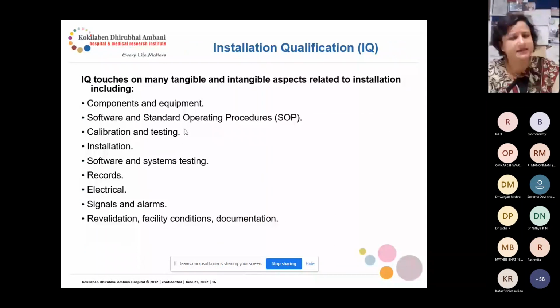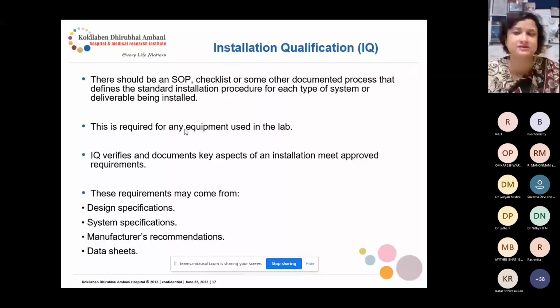So at various stages during IQ, you need to review, check, report, and authorize the protocol. You need to check the specification and the acceptance criteria. IQ touches many tangible and intangible aspects related to installation, including components and equipment, software and the standard operating procedure for your software, calibration and testing, installation, software and system testing, records, electrical testing, signals and alarms, revalidation, facility conditions, and documentation. So there should be an SOP, a checklist, and some other documented process that defines the standard installation procedure for each type of system or deliverable being installed. This is required for any equipment used in the lab.